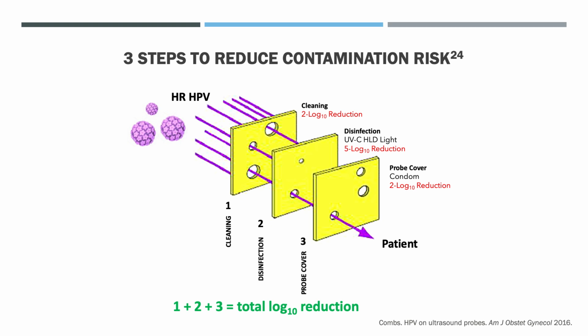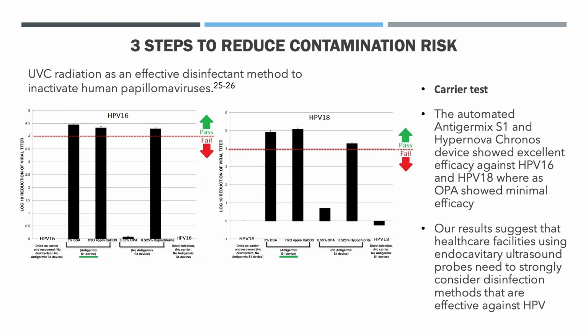So if you add all of those up, you end up with your total log reductions here, which would be, for this model, a 9 log reduction, which is substantially higher than any possible contamination on a probe. And here we're talking specifically about HPV. Again, 3 steps to reduce contamination risk. UVC radiation is an effective disinfection method to inactivate human papillomavirus.